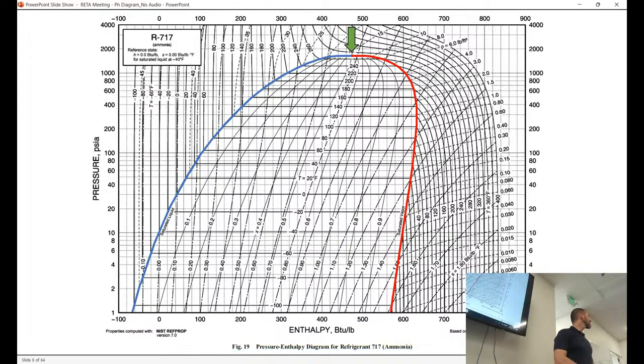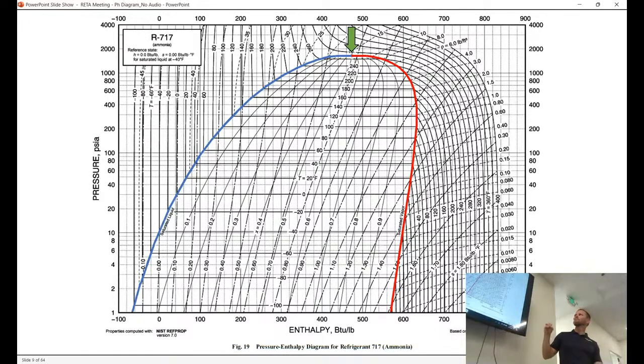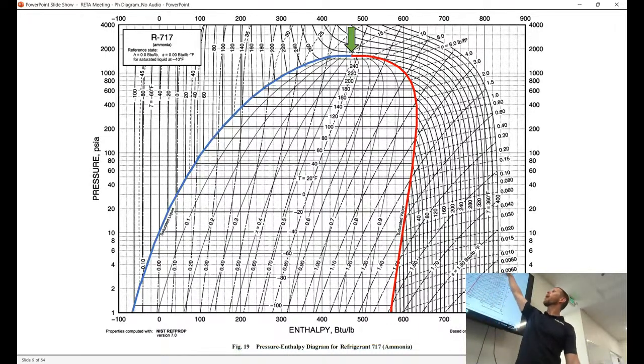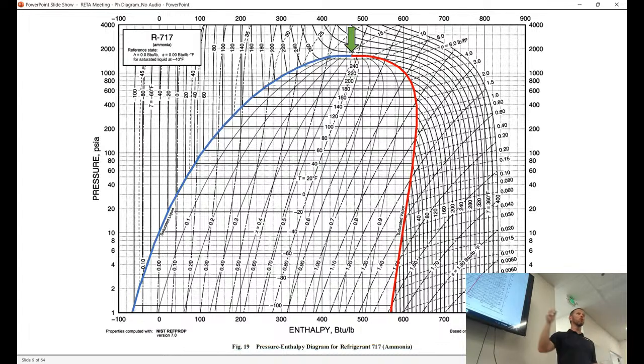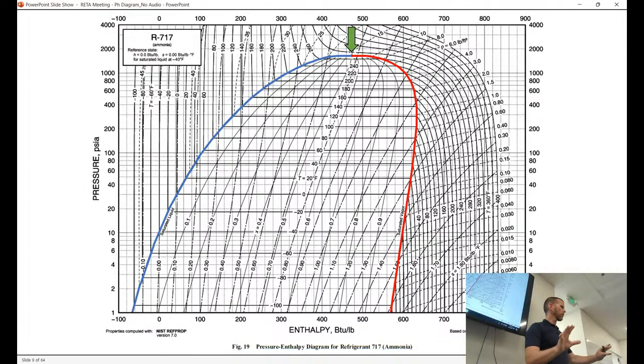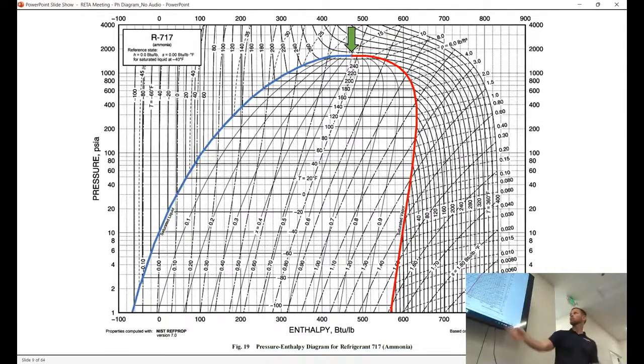This point right on top we have a fancy name for — we call it the critical point. Some folks have trans-critical CO2 systems. What does trans-critical mean? It means you're actually operating above that critical point, above the saturation dome, where you don't ever transition from liquid to vapor. You go straight from superheated vapor to sub-cooled liquid — we call that trans-critical. For the sake of today, we're looking at ammonia P-h diagrams, which will never be trans-critical. But when you hear trans-critical CO2, you're above that dome.